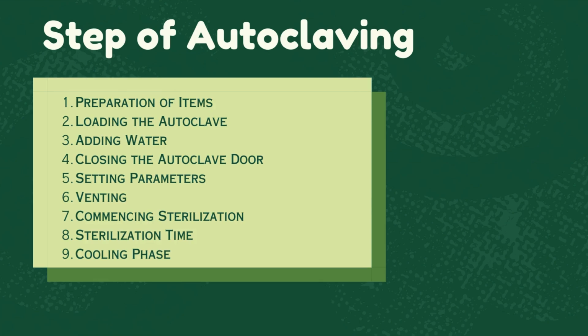Third is adding water. Add distilled or deionized water to the autoclave. The water is necessary to generate steam during the autoclaving process. Fourth, closing the autoclave door. Ensure that the autoclave door is securely closed. Many autoclaves have a locking mechanism to prevent accidental opening during operation. Fifth is setting parameters. Set the desired parameters on the autoclave control panel. This includes the temperature, pressure, and sterilization time. The specific settings will depend on the items being sterilized and the autoclave model.